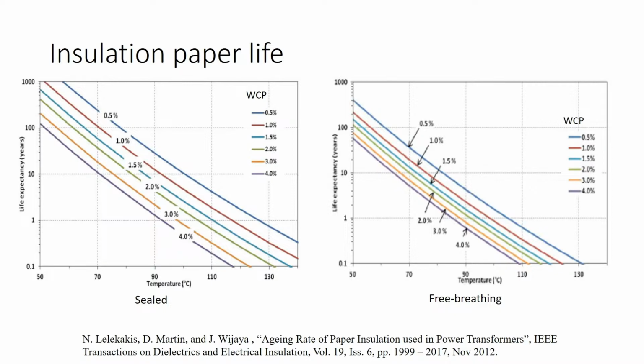So in terms of applying these graphs, we've got temperature along the x-axis. Normally, especially for sealed units, if you're looking at a continuous temperature, depending on its water content, usually between 70 and 90 degrees, then the life expectancy can be anywhere between 10 years and 100 years. So a utility may expect to get 30 years, 50, or even 70 years out of a transformer. And normally they would try to keep the conditions within that zone.